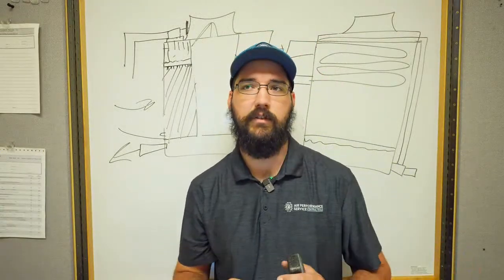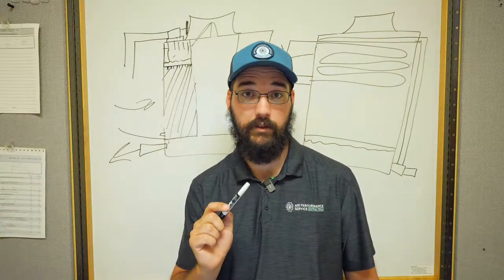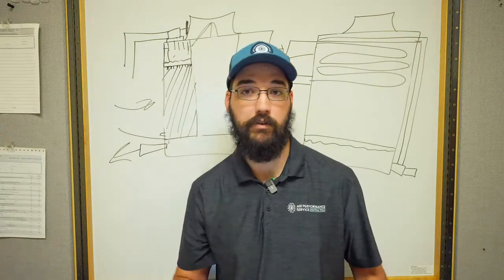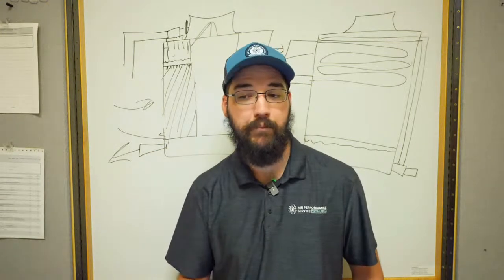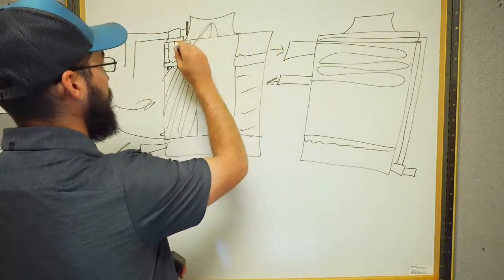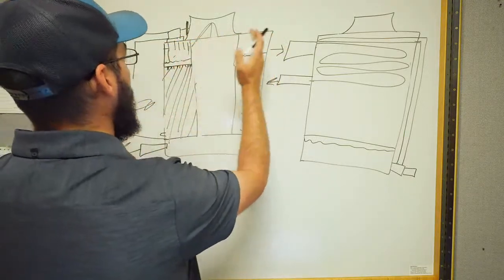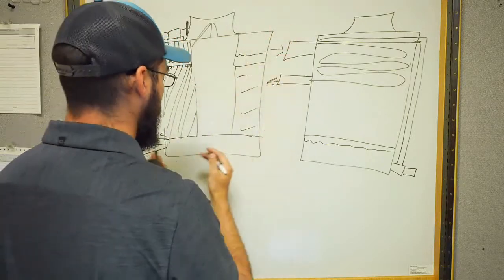Getting back to startup: balancing is part of startup, and how deep you go depends on the style of system and how well it was designed. The piping on the towers also plays a big part. If you're running a tower that has two decks on an open loop, you need the piping split as perfectly as possible.